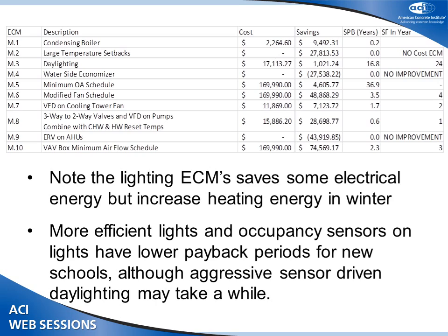Similarly, we got paybacks for other measures, and I just want to point a couple of these things out. I wasn't sure of this one, for instance, using variable frequency drives, which is growing in interest here. If you look at here, paybacks less than 2 years. All of these where I'm getting paybacks of less than 2 years are of interest to me because they are something that I can very easily incorporate, convince an owner that they're important, and then I can confirm with actual performance. This is what my model suggests to me.